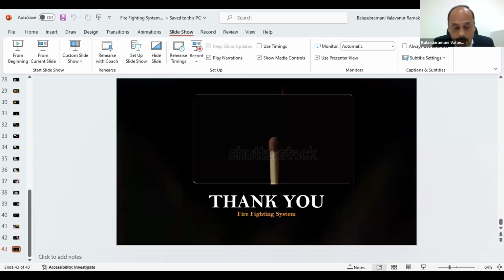Does it work for only the area where the sensor has detected the fire? Actually, there is not a separate sensor. The fire sprinkler bulb is there. It will detect when the fire occurs. There is a liquid in the bulb, with respect to the temperature, 57, 79, 93, depending on the temperature. The temperature and pressure are proportional. When the temperature increases, the pressure also increases. The moment it reaches a particular temperature, it breaks. Then it gives feedback to the relevant pump, the jockey pump, and then subsequently the electrical or diesel pump comes into the picture to spray water on the fire rated area. Perfect. It will pour water on that particular area, not on all the area, in the case of a sprinkler. Okay, thank you, Mr. Bala.